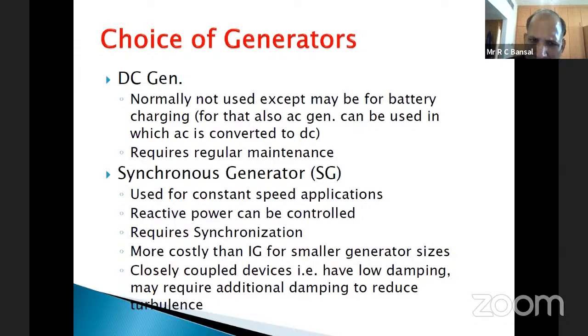Synchronous generators are basically used for constant speed applications - they run at constant speed. We can control the reactive power. The synchronous generator will require synchronization, and can only run at synchronous speed. So synchronous generators are generally more costly than induction generators for small size generators, like those used in hybrid power systems or as standby generators.